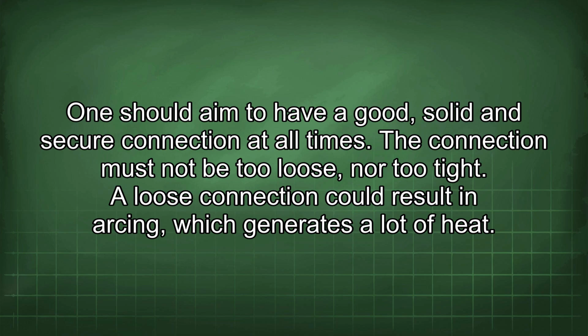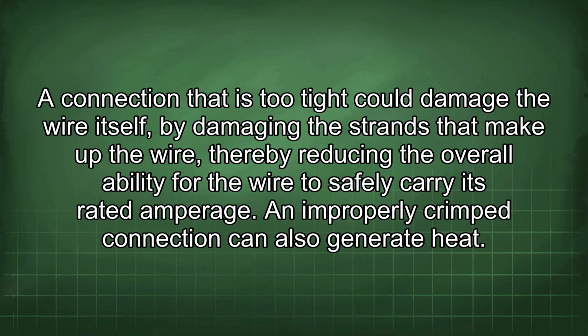The connection must not be too loose, nor too tight. A loose connection could result in arcing, which generates a lot of heat. A connection that is too tight could damage the wire itself by damaging the strands that make up the wire, thereby reducing the overall ability for the wire to safely carry its rated amperage. An improperly crimped connection can also generate heat.